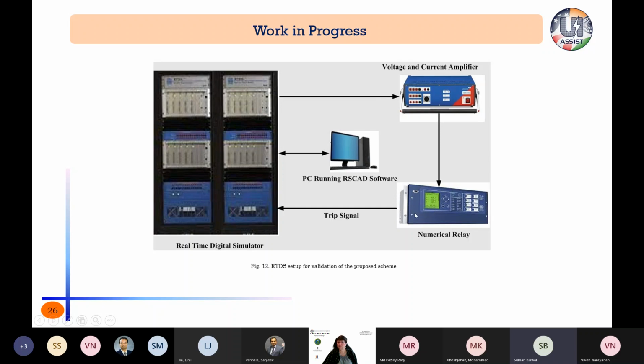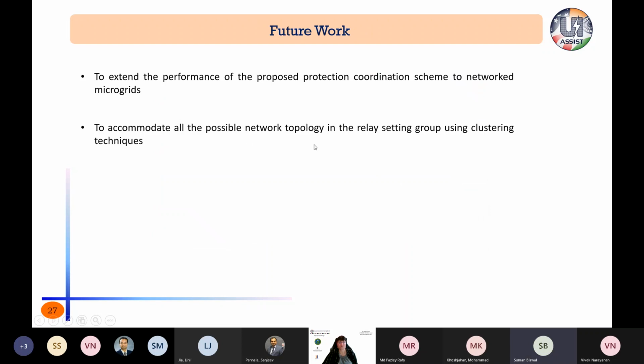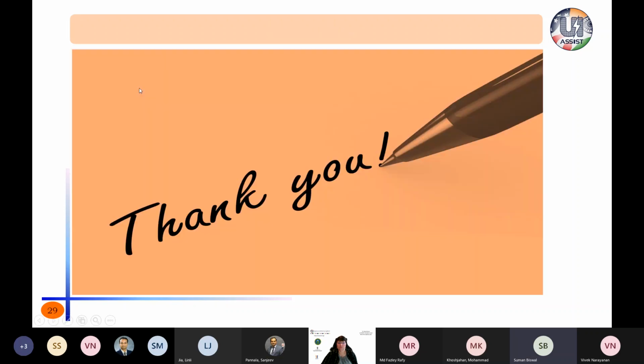So the digital signal from the numerical relay will be fed back to the digital input, or GTDI, of the RTDS. Then the corresponding breaker will operate. In this way, the coordination or the HIL validation can also be done for this work. Currently I'm doing it, it's not completed, and very soon I will finish it. And the future work includes the concept of network microgrids. So instead of taking one microgrid, we can consider the protection coordination for network microgrids as well. And also, since the number of operating modes increases, we need to apply some clustering methods, so that whatever relay setting groups are available can accommodate that, for better operation. So this is future work, and these are some of the references.